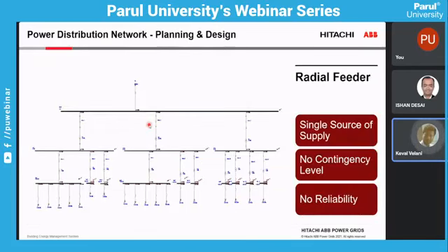This is a typical distribution network as a radial feeder. In a radial feeder, there are three features: single source of supply, no contingency level, no reliability level. Here you can see the single radial feeder coming from the power source, this is the main incoming bus, and then three circuits in this power distribution network. Again, in one circuit, it is distributed into three more circuits. Here in the second source, main circuit, three sub circuits, and this is the sub distribution. Each and every circuit and equipment has only one source of supply available, so there is no contingency or reliability level provided in this planning and design as a radial system network.